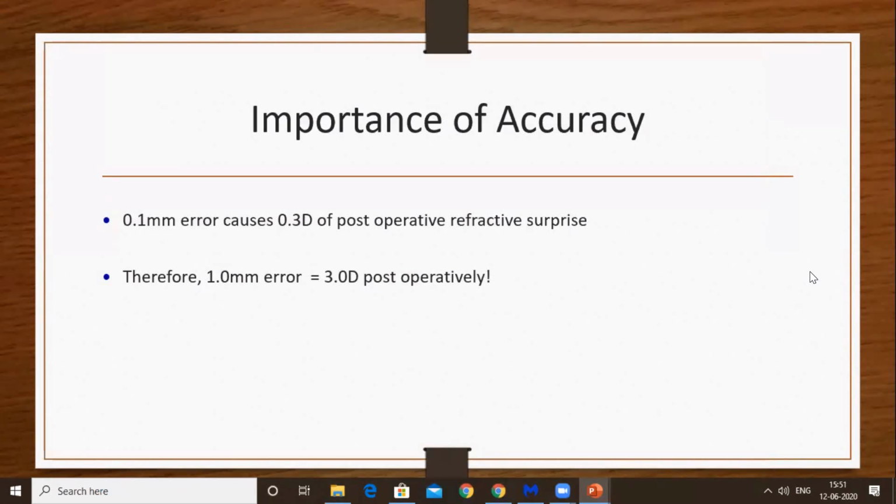So before finalizing the axial length measurement, you should cross-check with 2 or 3 tries whenever you are doing a normal ultrasound A-scan. But in cases of non-contact, it is not advisable to go for multiple readings. You can go with two readings.